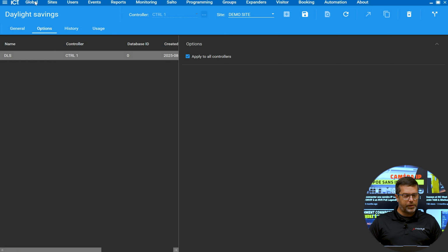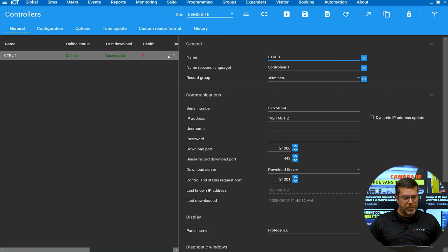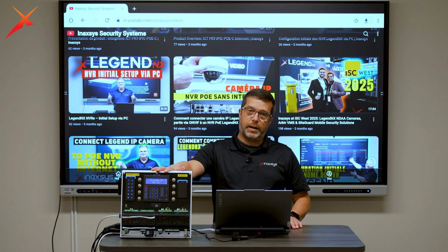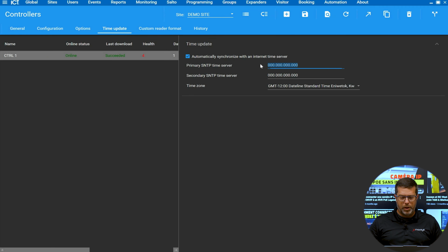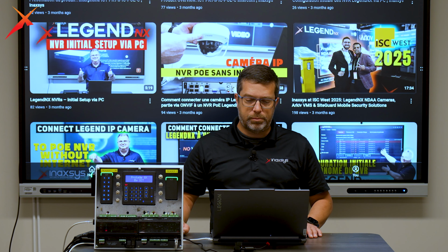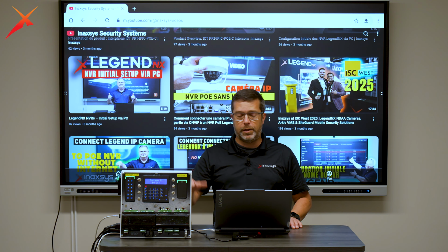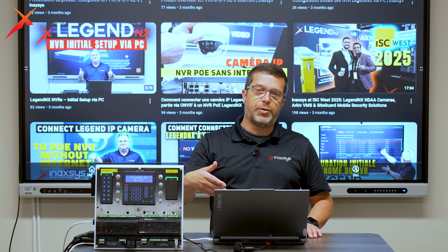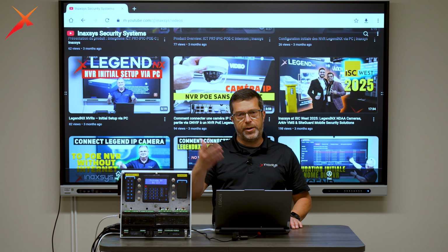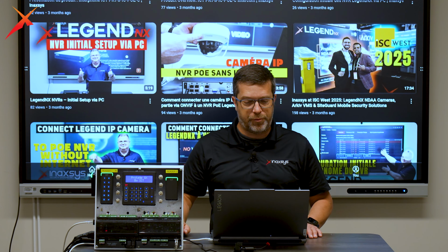One of the things I like to do is to go in the controller properties and the time update. This is not connected to the internet at the moment. If it was, I would suggest that you enable the time server. I like to use the Google primary and secondary IP addresses in there because they never change, but I don't have an internet connection, so I don't use it. But make sure that if your controller is connected to the internet, you have a time server. If it's offline, most of the time you can use the router or even a managed switch from various manufacturers that have an NTP server in them, so you can use the address of the router or the switch for this application.